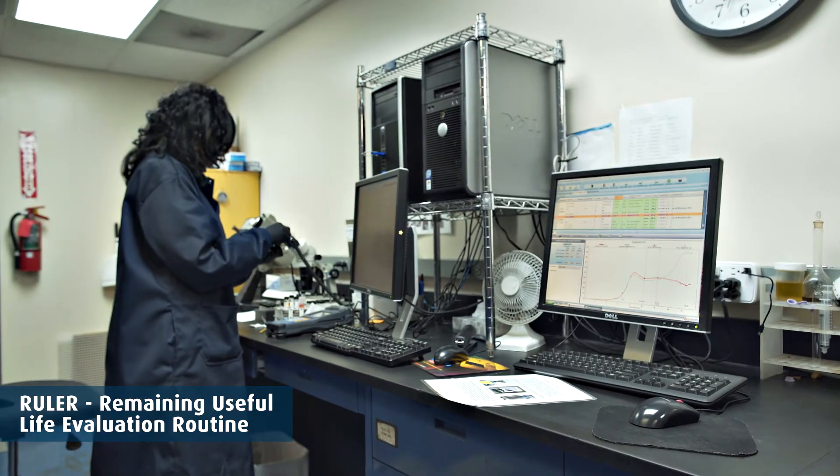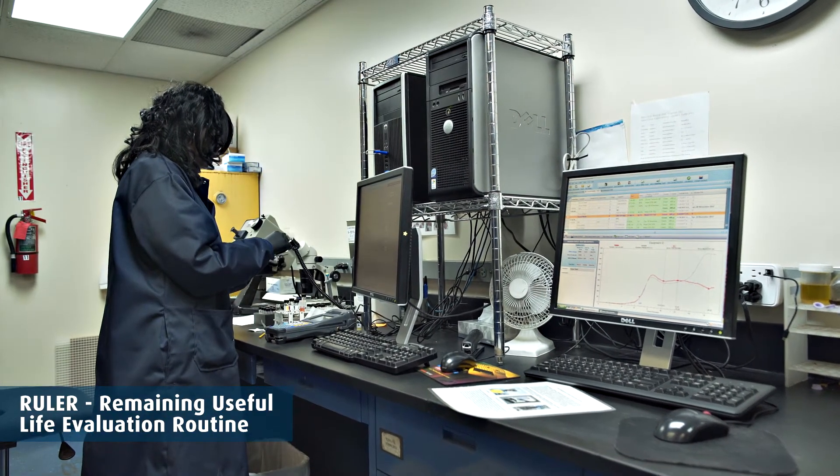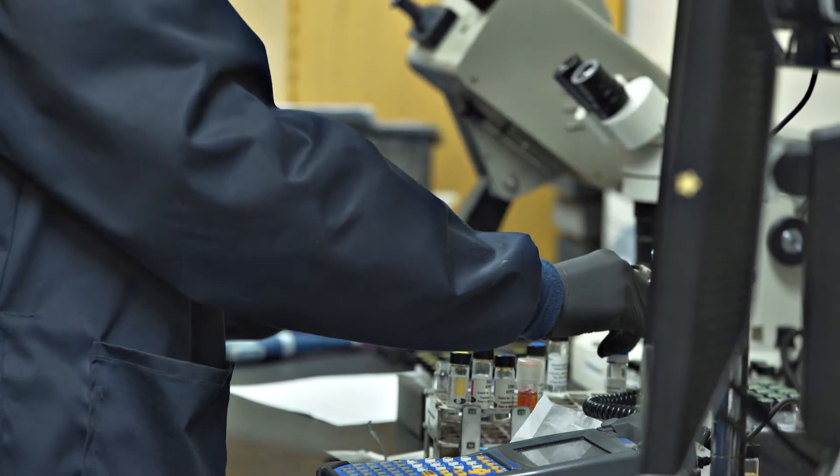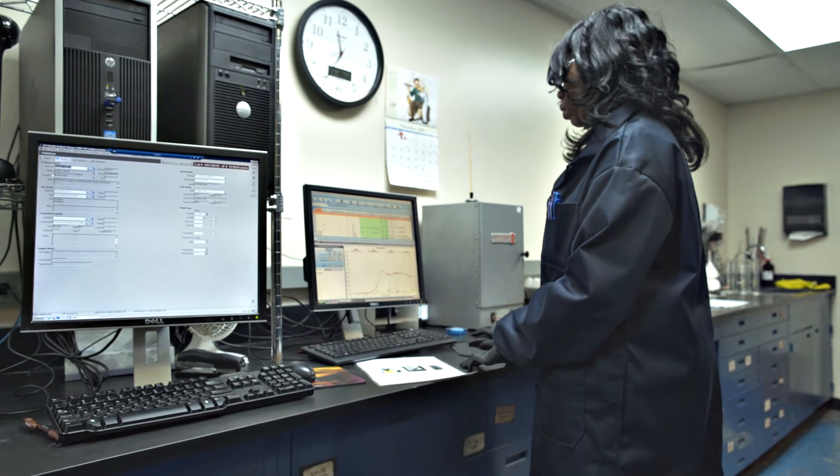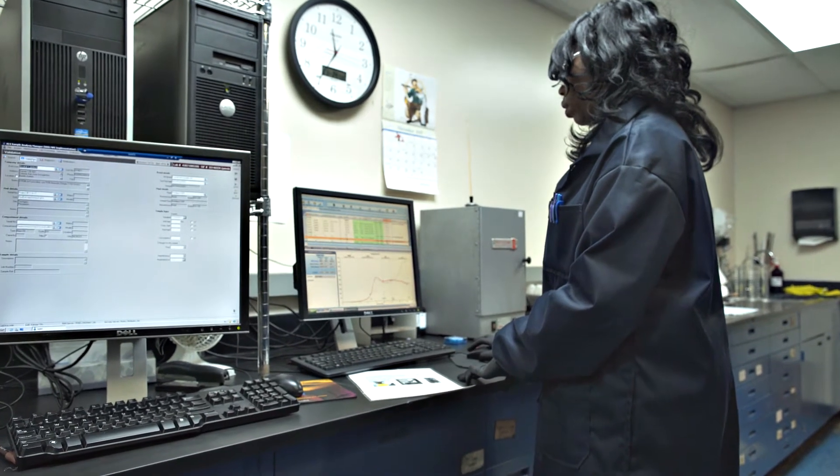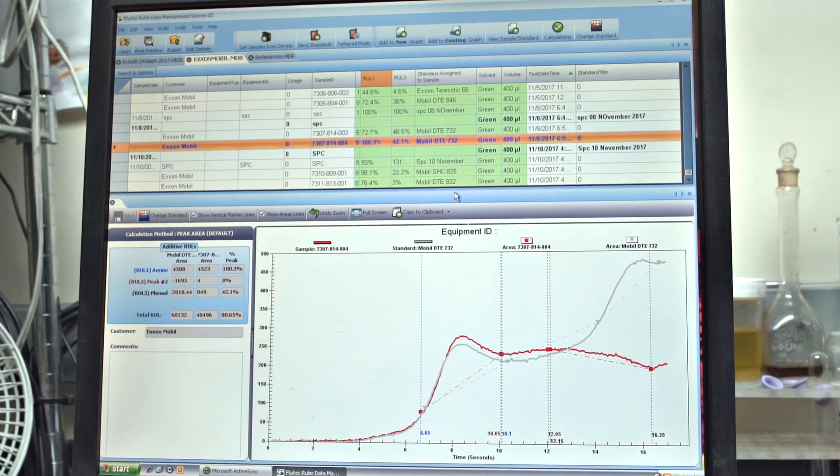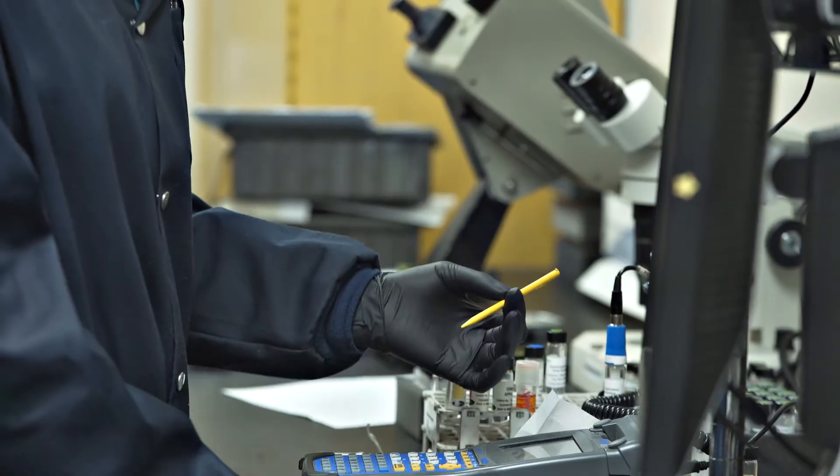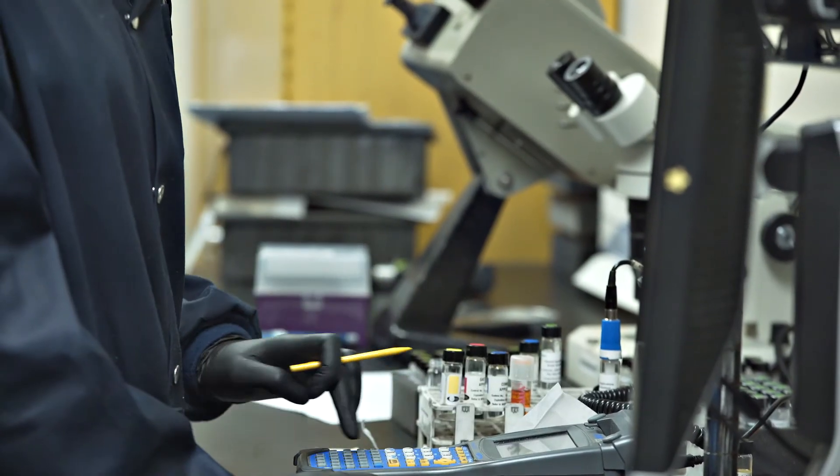RULER, remaining useful life evaluation routine. This test method measures the remaining level of active antioxidant additives in a fluid. This test can be used as a standalone test and is also a key ingredient in the test matrix ALS Tribology provides for determination of varnish potential in turbine and industrial fluids.